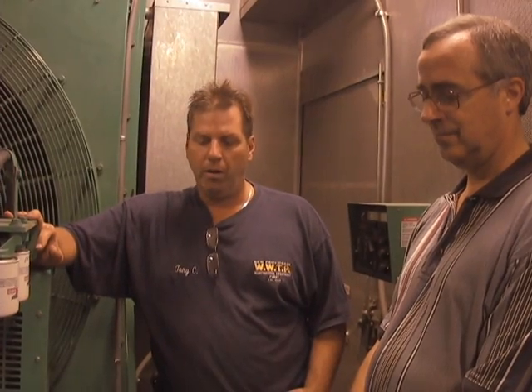So what normally happens when there's a power failure, there's an automatic transfer switch that senses it, isolates the plant from the utility grid, and switches it over to this power supply. And that happens very quickly. Within a matter of a minute or so, you're up and running again. But when the automatic transfer switch isn't working, someone has to come over here and manually do that. It all depends on how long it takes the person to get there. And then once he does, he's got to throw the switch and start this up. You could be talking at least a half an hour. Yeah, if not more. And if your wet well doesn't have the capacity, you're going to flood. So that was a very important thing, and we were able to reprogram the processor over there, get it out of halt, and then we found a bad 2447 monitoring relay that was in the system.